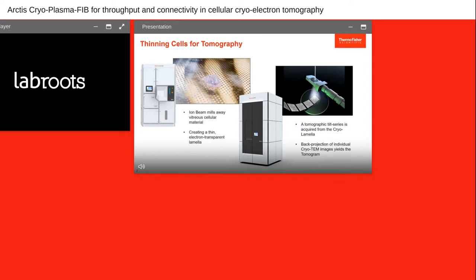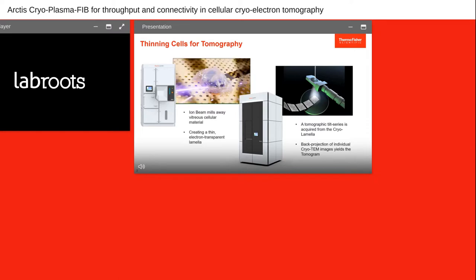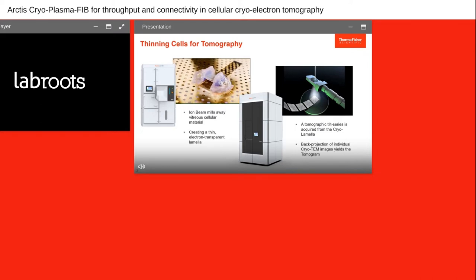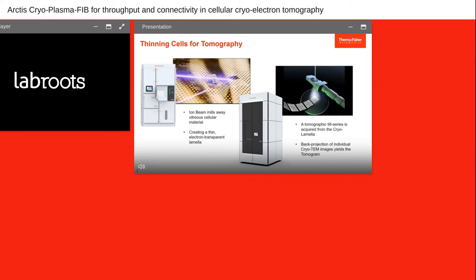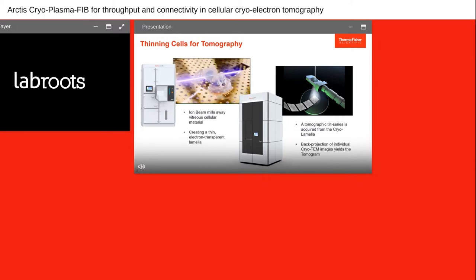Thank you for the introduction. Welcome to this Arctis cryo-plasma FIB webinar. The Arctis system is our new sample preparation system for electron tomography. The Arctis uses a focused ion beam — in this case a plasma focused ion beam — to thin cells down to make them electron transparent so that we can image them in the transmission electron microscope. The Arctis produces an ion beam that we direct site-specifically to a frozen hydrated cell, which typically resides on an electron microscopy grid. We use this beam to mill away cellular material and thereby create a thin, electron-transparent lamella. These in-situ lamellae provide a view into the frozen hydrated interior of the cell.